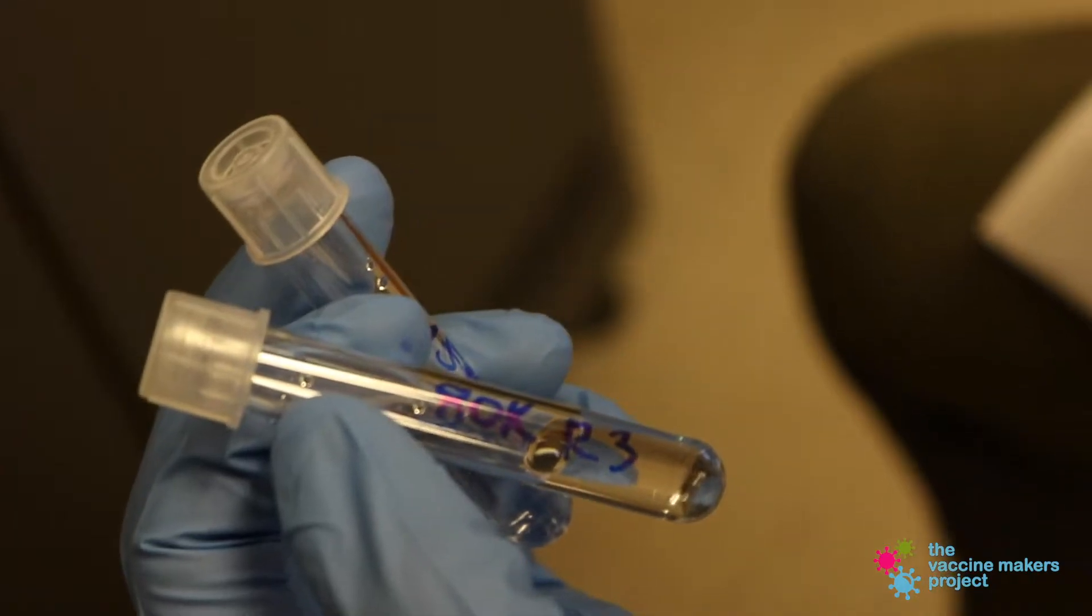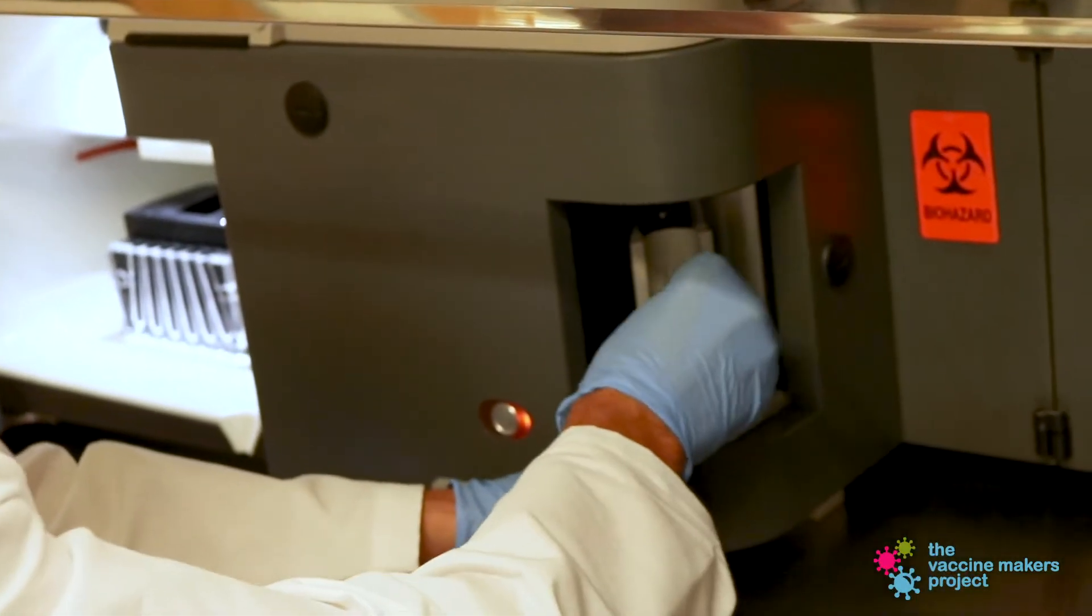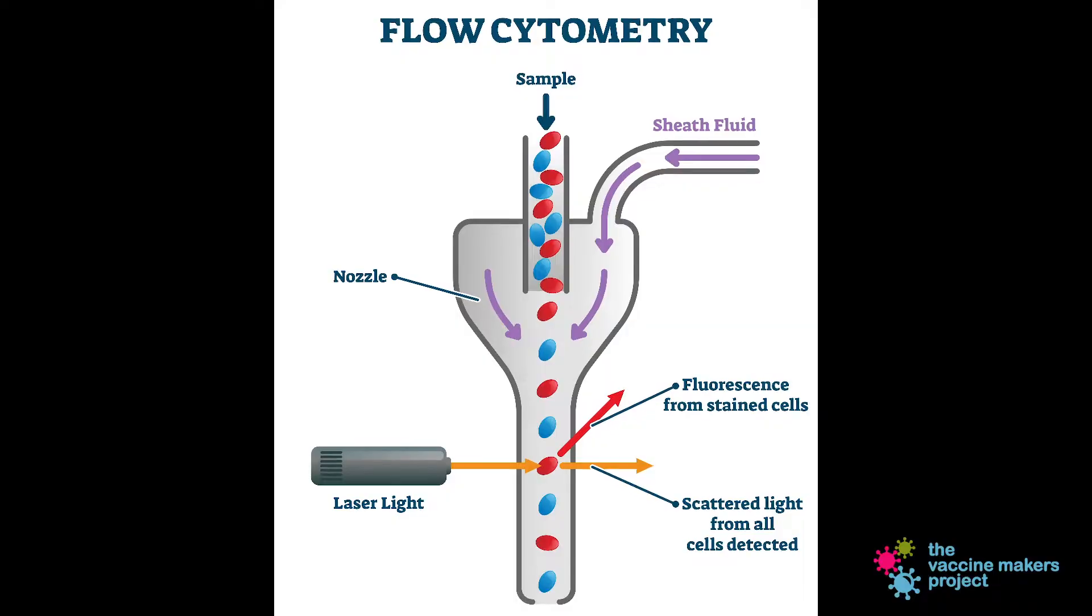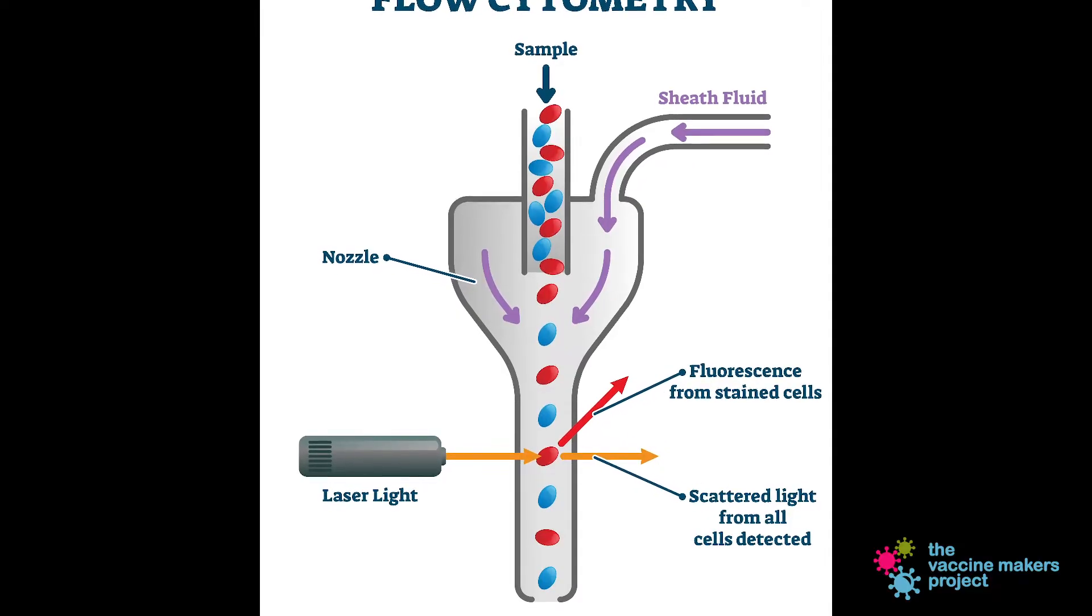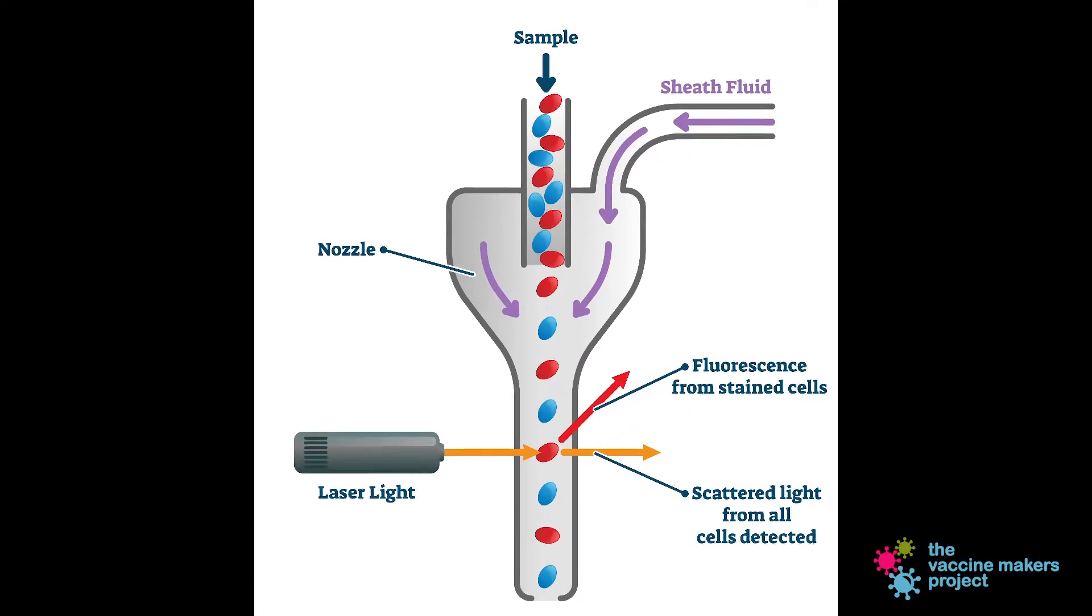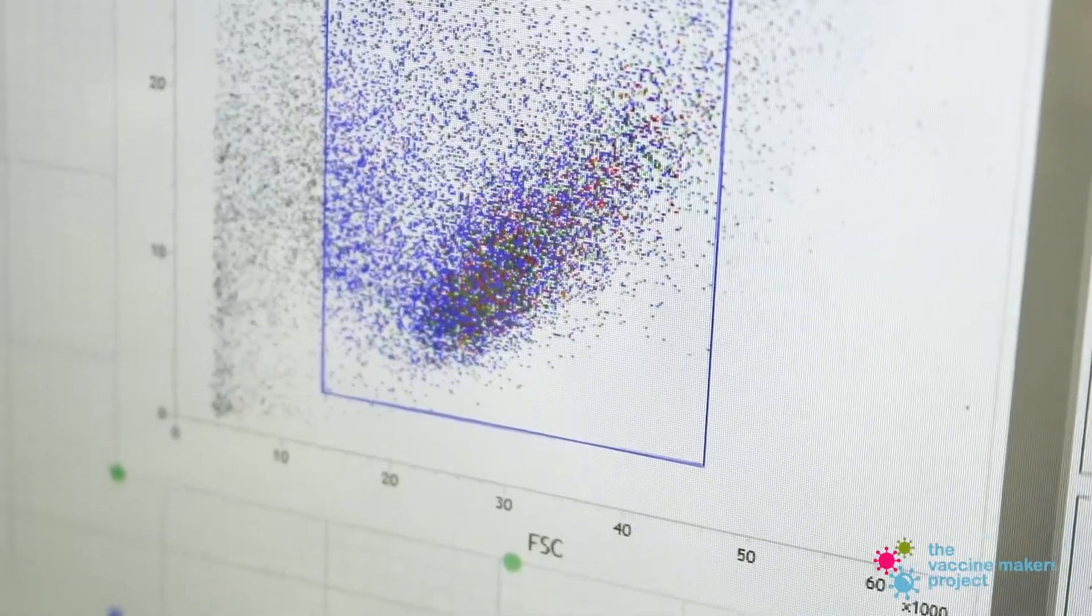To prepare cells, the cells of interest are marked with a fluorescent label. As each cell passes through the machine, it goes past a laser or several lasers. The laser excites the fluorescent tag, creates a pulse. This pulse is read by the instrumentation and then shows up as a dot on a graph.